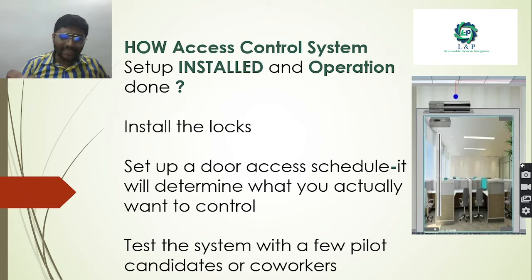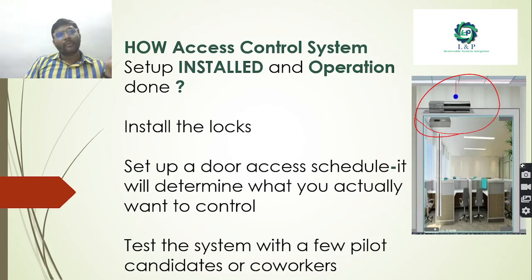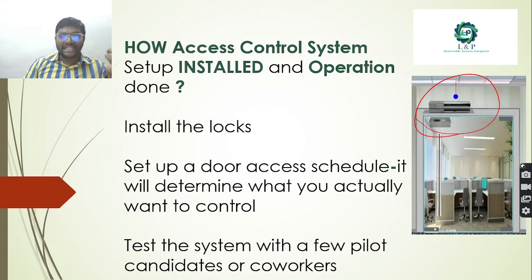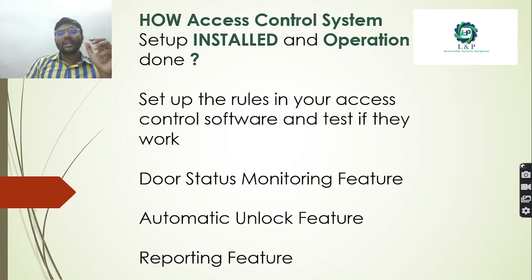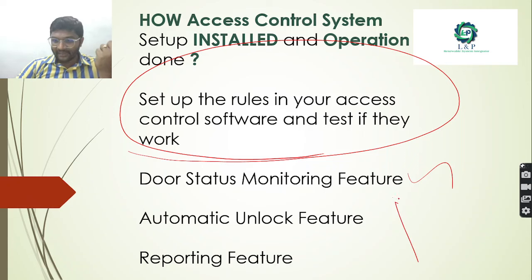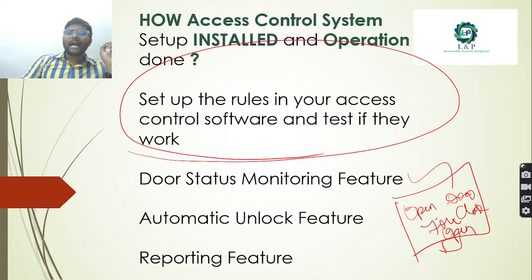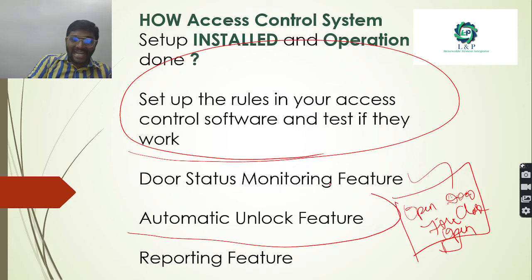After installation setup, we need to create a door schedule — defining when doors unlock automatically without card readers and when they should be locked. Door status must be monitored from the server to know whether a concerned door is open or not. During fire scenarios, an automatic unlock feature must be available.